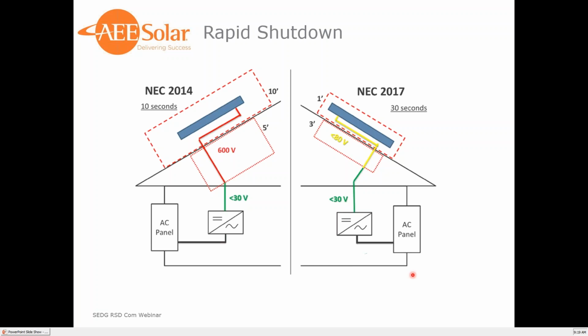NEC 2017 is the 1-foot array perimeter with 3-foot penetration through the building. Now inside that perimeter, within the 1 foot and the 3-foot penetration, it would be required to be less than 80 volts. And then the controlled conductors leaving the array are required to be less than 30 volts.